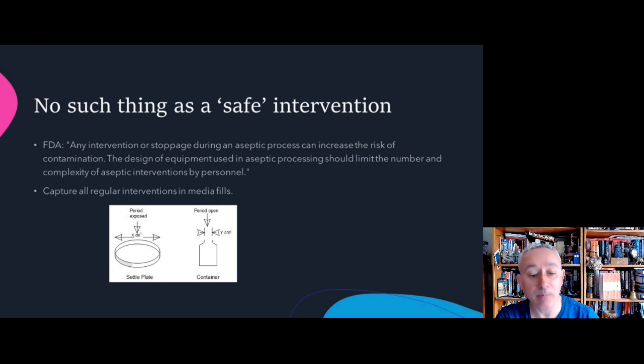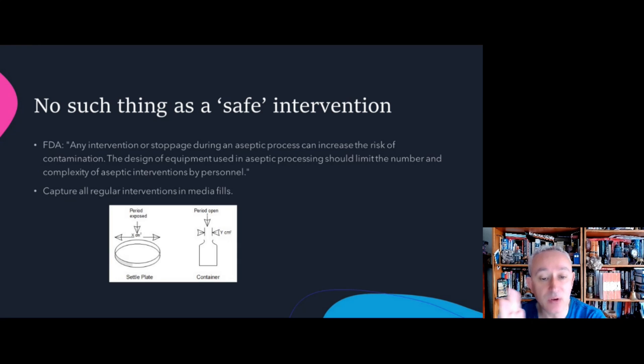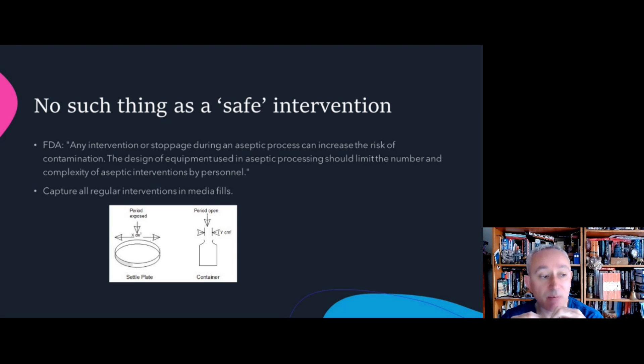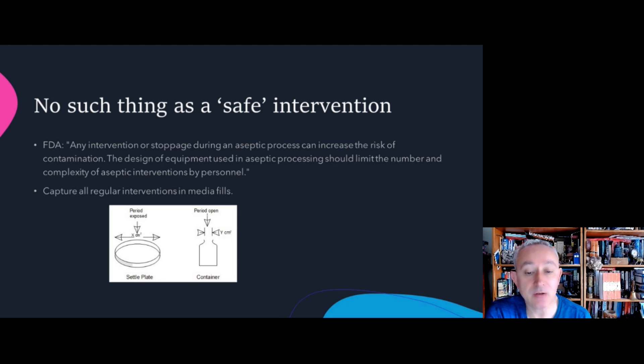It could be asked: what is the perfect intervention? The perfect intervention is no intervention whatsoever, because there is no such thing as a safe intervention. The FDA guidance states that any intervention or stoppage during aseptic processing can increase the risk of contamination, and the design of equipment should try to limit the number and complexity of aseptic interventions by personnel. To assess risk, the standard approach considers the criticality — severity versus frequency of occurrence — but with aseptic processing, assessing the severity of occurrence is very difficult.